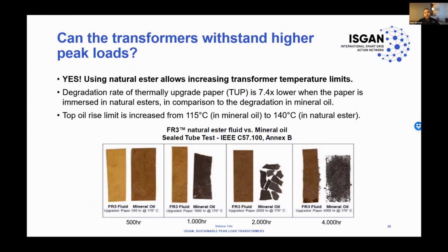So it's 7.4 times lower. The result of this is a possible increase of 20 degrees in the thermal class for the very same paper. So you see here on the screen, aging side by side. This is a high temperature aging at 170 degrees. And you see that after 1,000 hours, the paper that was aged in mineral oil is already very brittle and black and very fragile. And even after 4,000 hours, the paper that was aged in FR3 fluid, in a natural ester, was still brown, almost looking like the paper immersed in mineral oil after 500 hours. If you could move to the next.